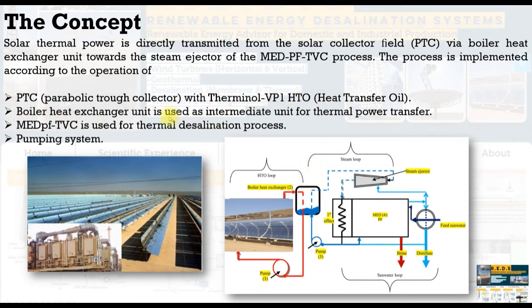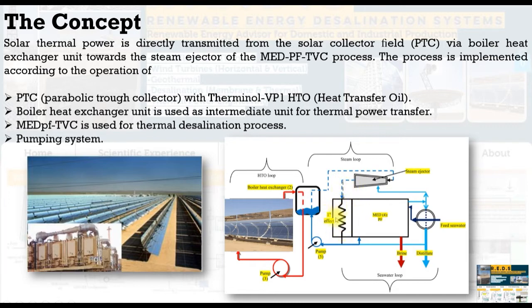A boiler heat exchanger unit is used as an intermediate unit for thermal power transfer or conversion. The steam ejector uses the motive steam to power the MED thermal vapor compression. This is the Parabolic Trough Collector and the heat transfer loop using oil, in order to transfer the thermal power from the solar field to the intermediate boiler heat exchanger unit, which generates steam as motive steam to the steam ejector.